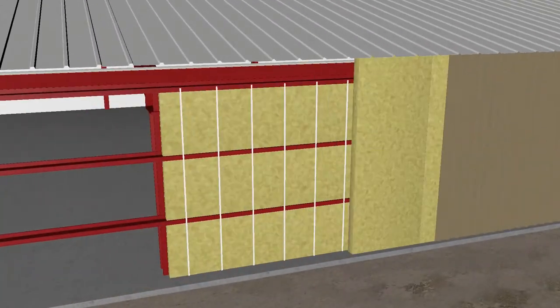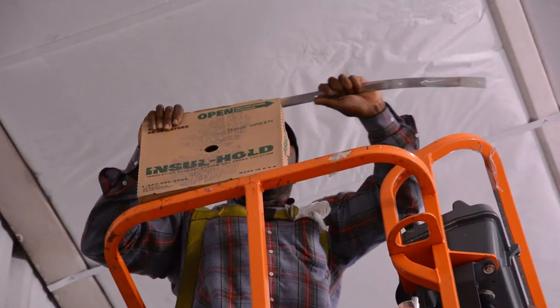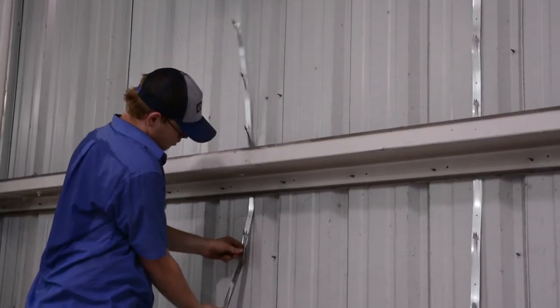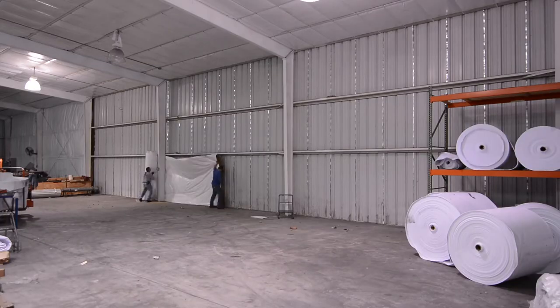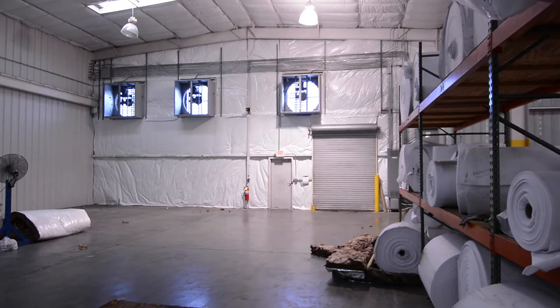Insul-hold steel bands with die-cut prongs are used to support additional insulation blankets placed between the steel wall girts. The prongs penetrate the fiberglass from the back side and help support it from sagging. This system allows the owner to increase the R-value in the wall for both new and retrofit construction.